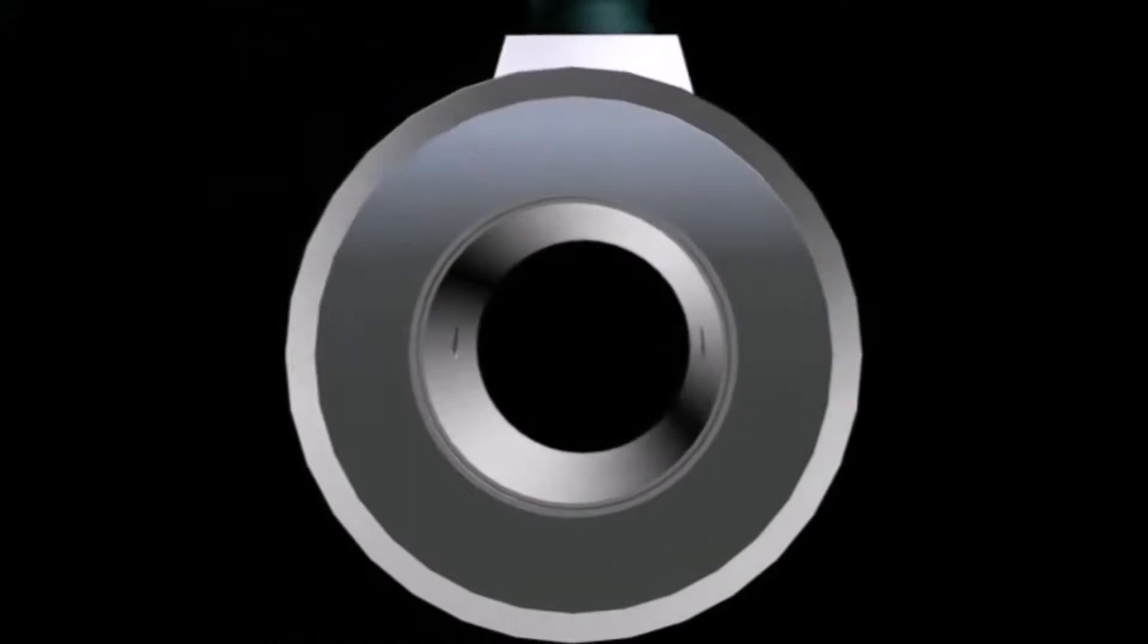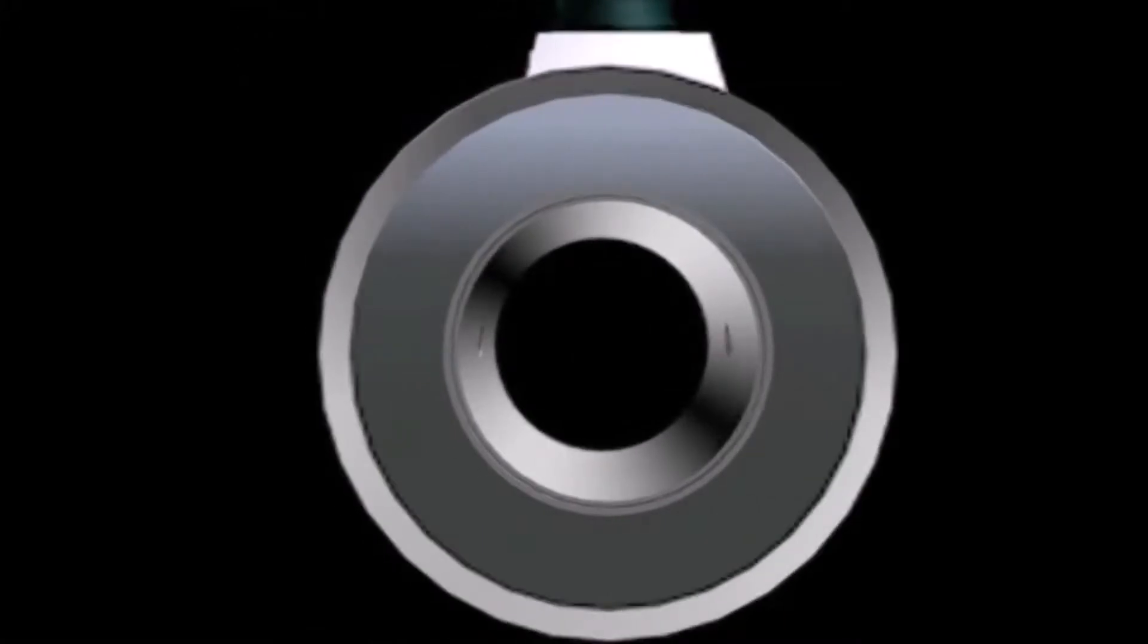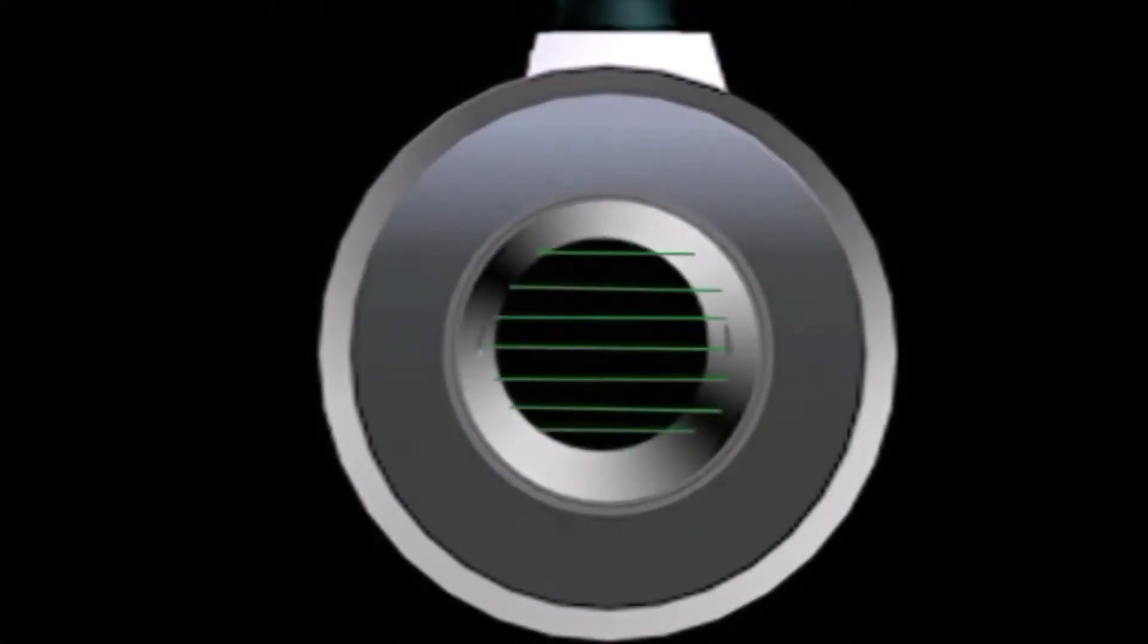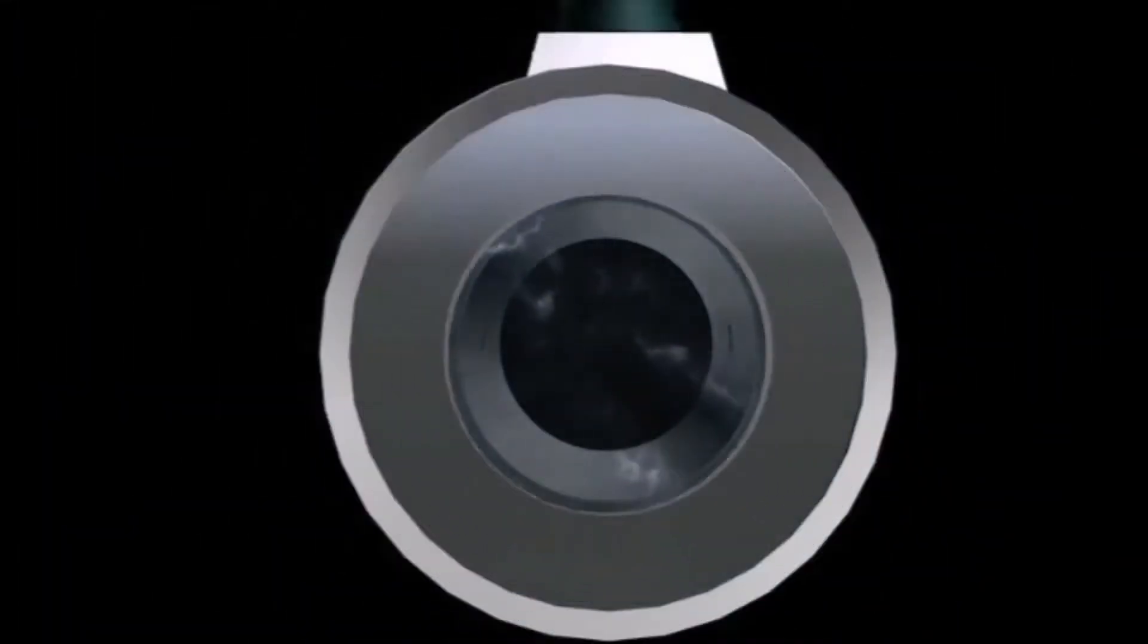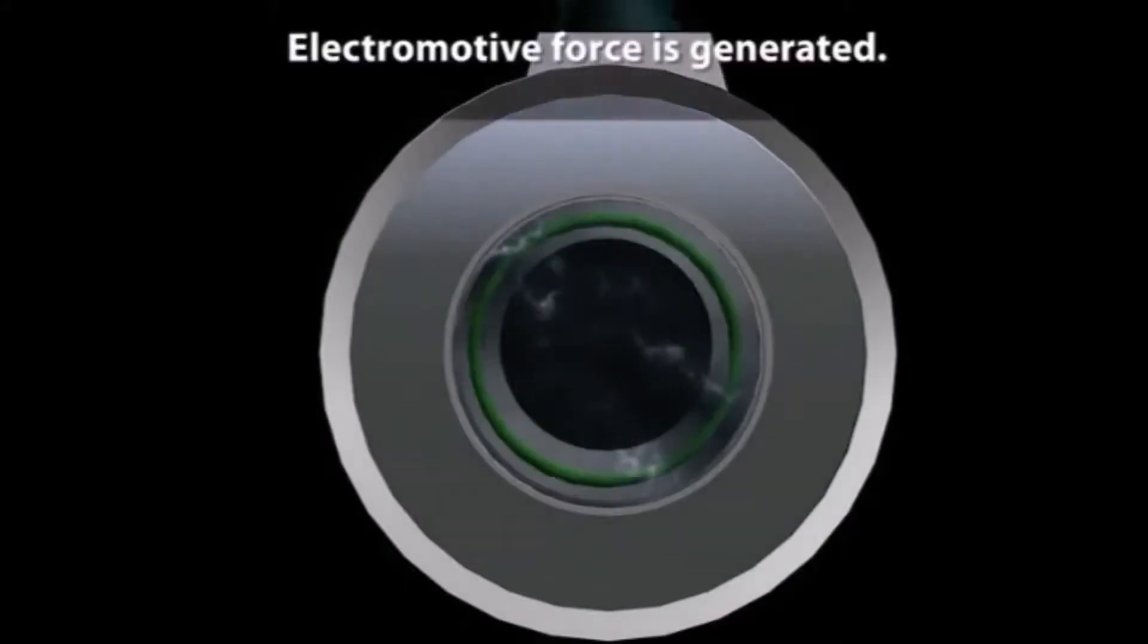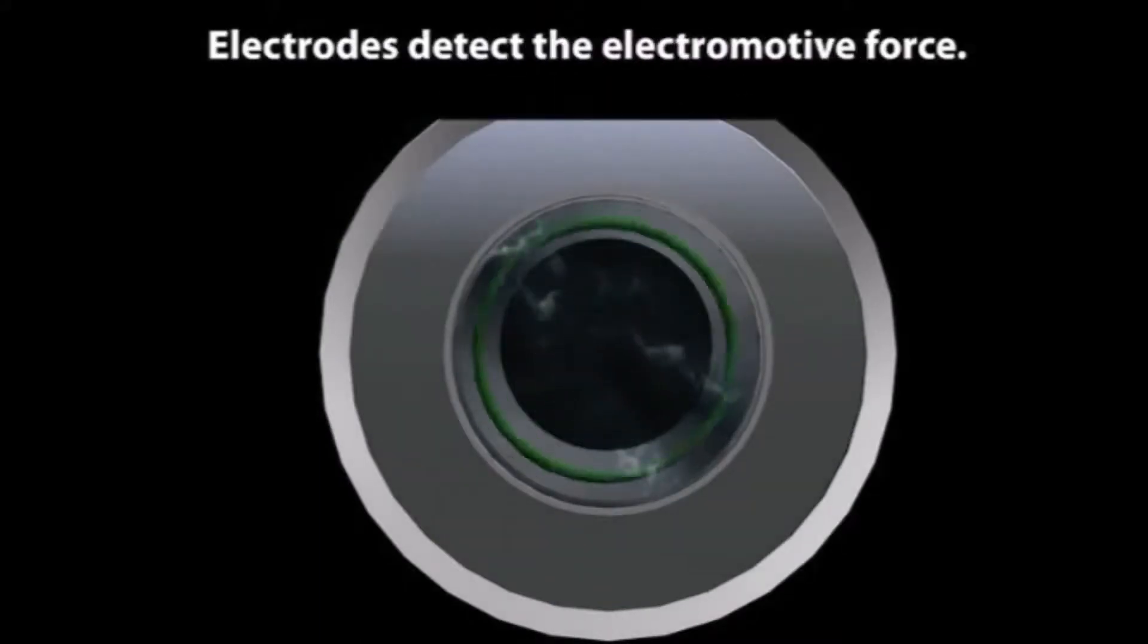Magnetic flow meters are built so the direction of the magnetic field is perpendicular to the flow, and the line between the electrodes is also perpendicular to the flow. As a conductive liquid flows through the flow tube, an electromotive force is generated. The electrodes detect the electromotive force.